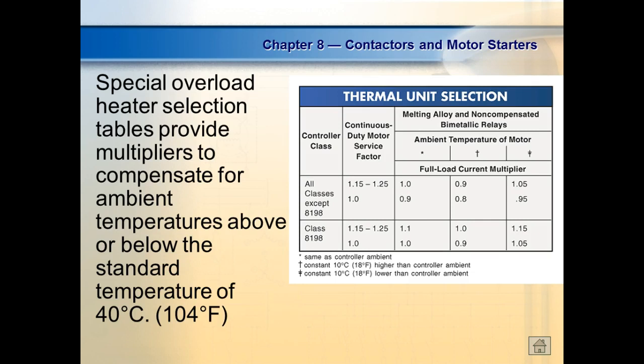Yeah, because that solder melts at a certain temperature. Well, if it's already at a certain heat, then that means it's going to melt faster, right? Does that make sense? So if you run it below that, so as long as I'm running below 40 degrees centigrade, then we're okay. It really comes into play if the ambient temperature of our overloads, not the motor, if the ambient temperature of our overloads is over 40, the rating of the motor, that's why we're going to have to derate that thing, right? Does that make sense?